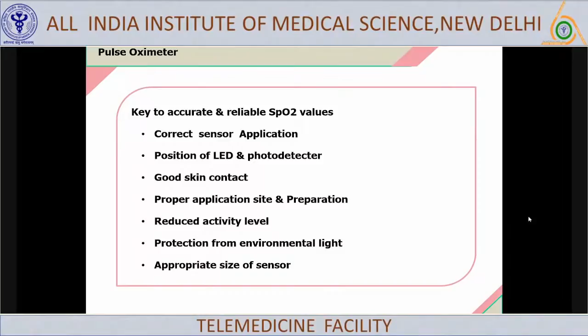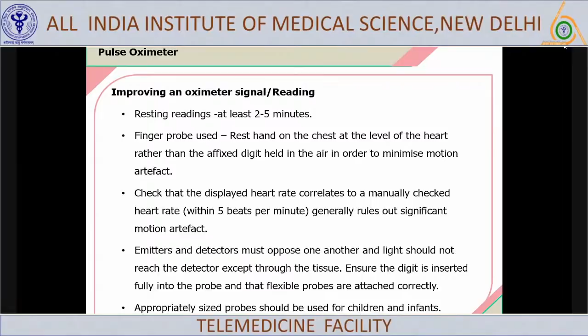Protection from the environment light: if there is a lot of light falling on the probe, it will again show an erroneous reading. And use an appropriate size of the sensor. So when you apply it, this is for us to understand, and also to help the caregivers understand. When you apply them, let it stay for a couple of seconds and take the readings at least at 2 to 5 minutes, when it has stabilized. Let the hand rest on the chest at the level of the heart rather than dangling in the air. Check that the displayed heart rate correlates to a manually checked heart rate.